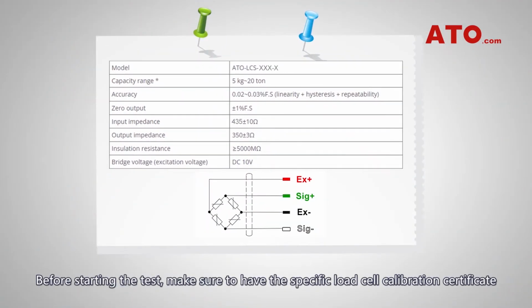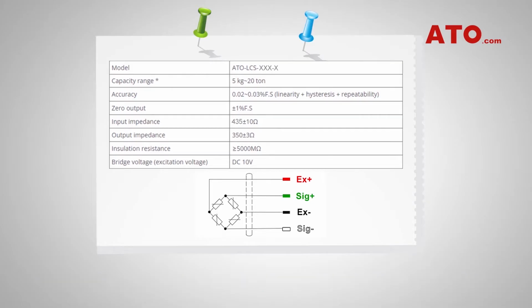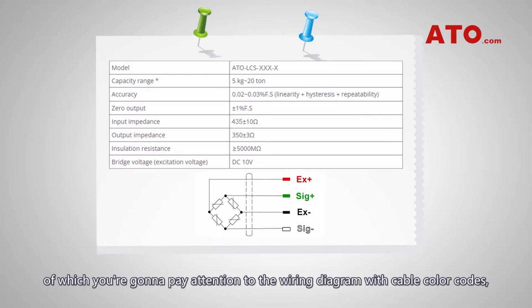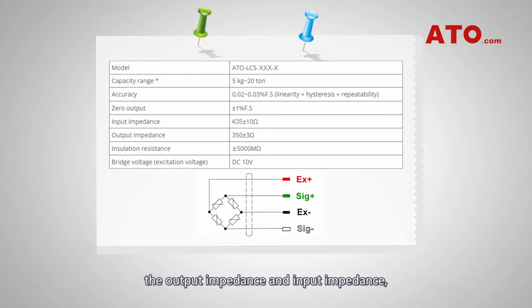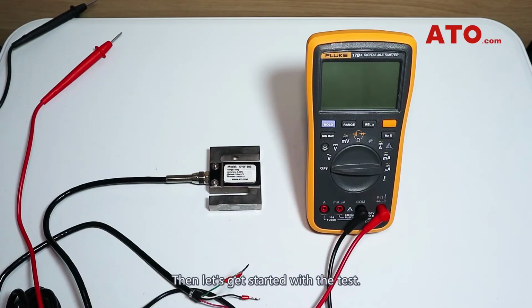Before starting the test, make sure to have the specific load cell calibration certificate, of which you're going to pay attention to the wiring diagram with cable color codes, the output impedance and input impedance, and anything else that's necessary for your testing purposes. After each test, remember to compare the measurement values with the calibration certificate from the manufacturer to see if they closely match each other. Then, let's get started with the test.